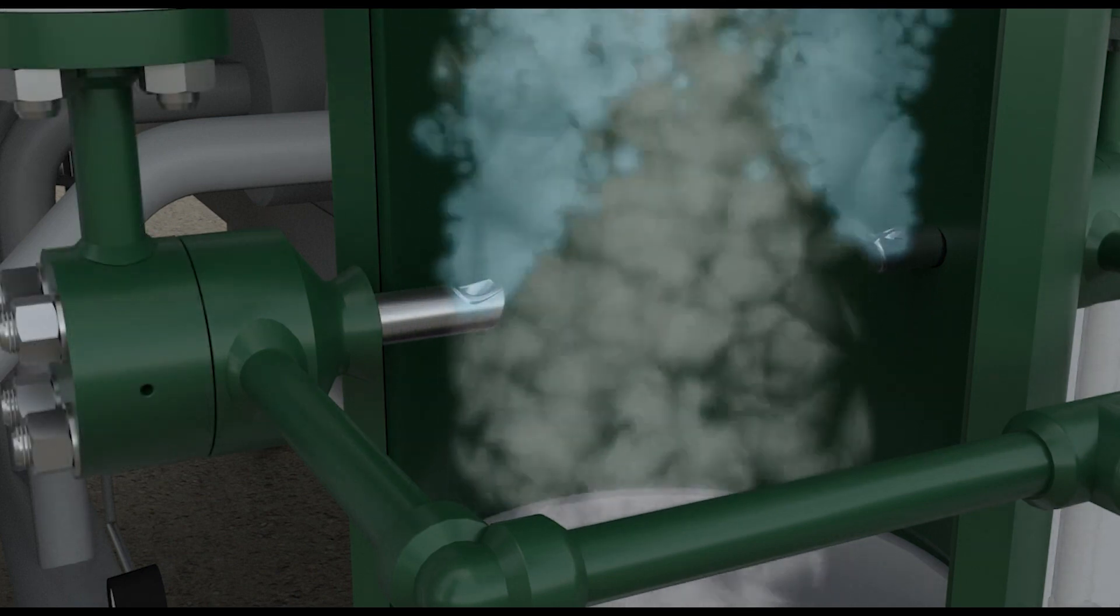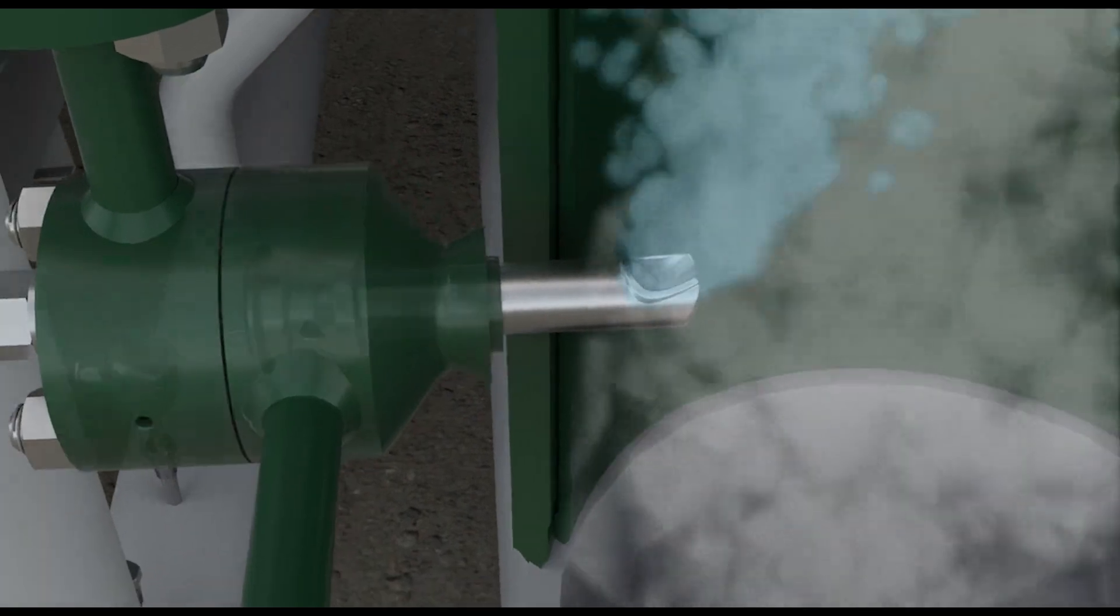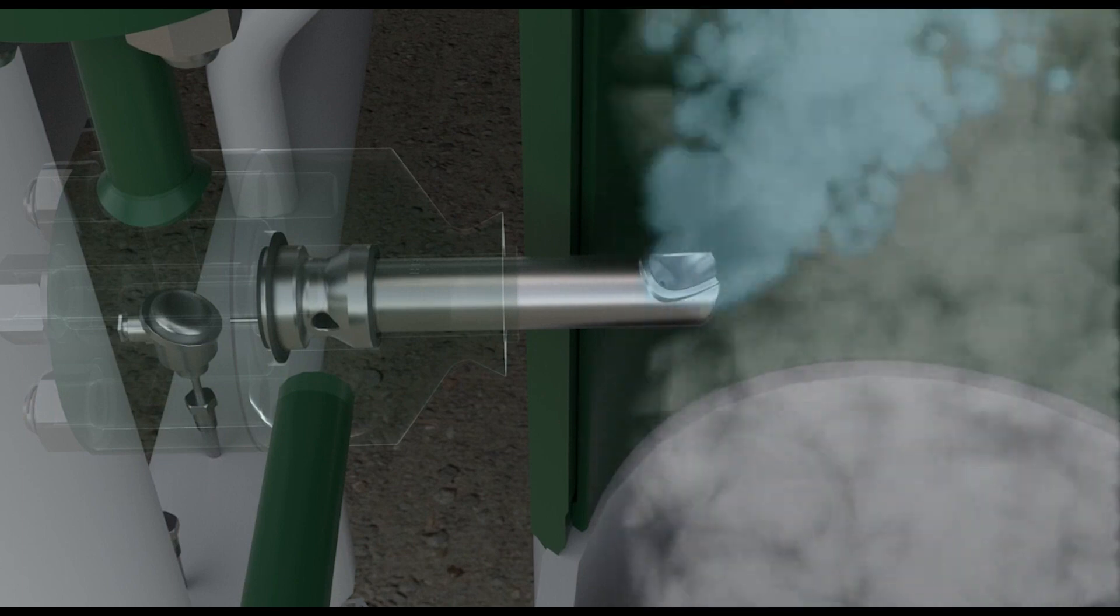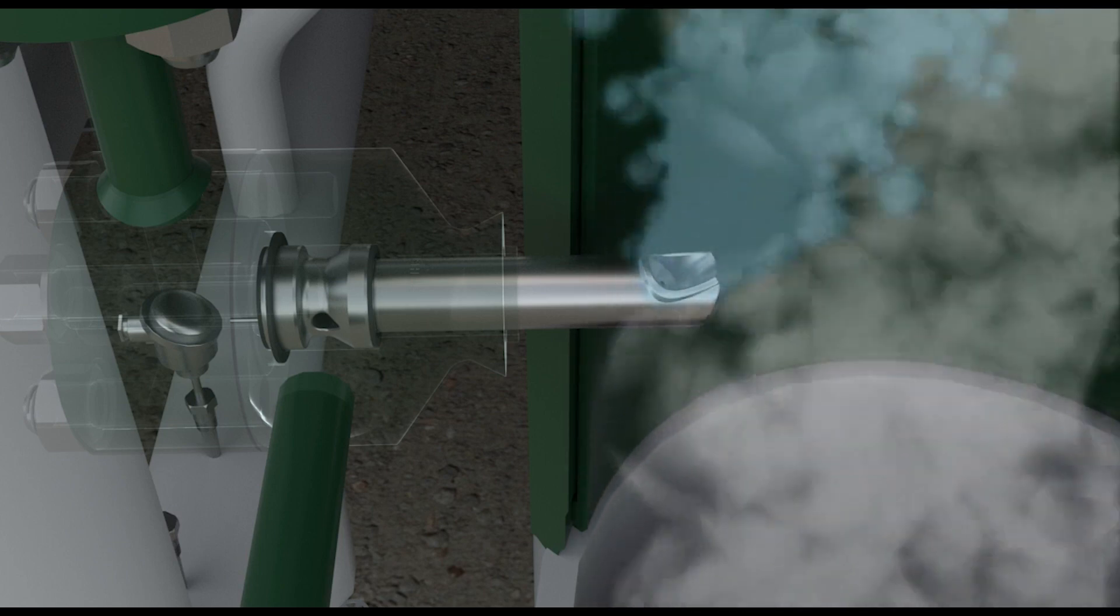The Fisher AT-ST steam atomized attemperator can help combined cycle power plants maintain ideal steam temperature under these load changes. The attemperator features an innovative spray nozzle that uses high-speed vapor to atomize water into a fog-like mist and has a much wider operating range.